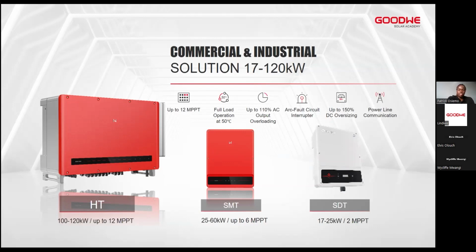An additional feature, which is optional and needs to be pre-ordered, is the arc-fault circuit interrupter, just in case you need your insurance to be valid. The arc-fault circuit interrupter will allow you to sense any arc faults on the PV DC side of the inverter, and the inverter will go to standby, thus ensuring safety of your installation. All these series allow an additional 50% DC oversizing, just to increase your self-consumption, increase your generation output, or counter the losses that will happen on the PV side or the DC cable losses on your PV installation. So yes, 150% DC oversizing.